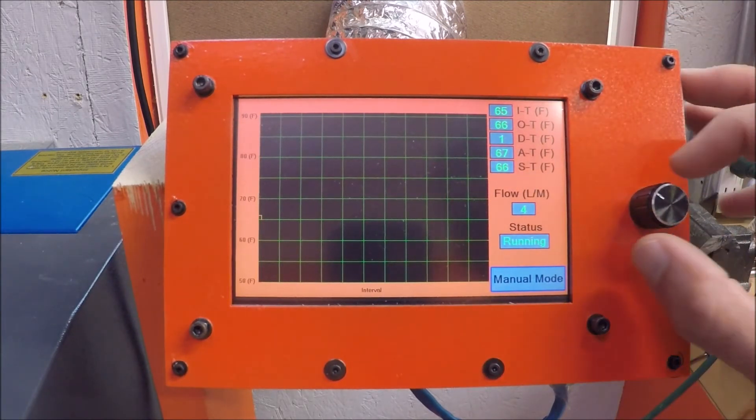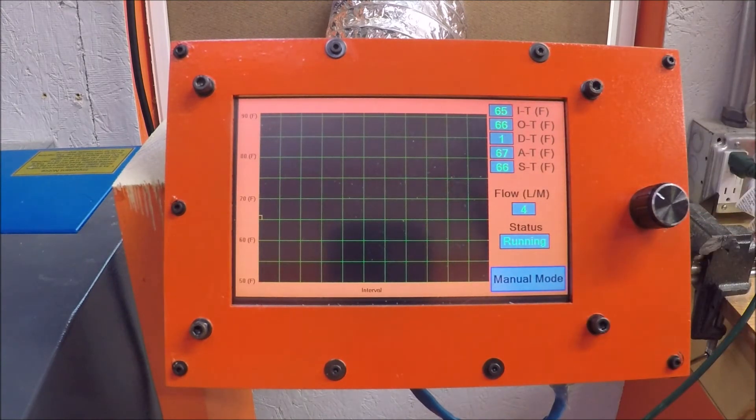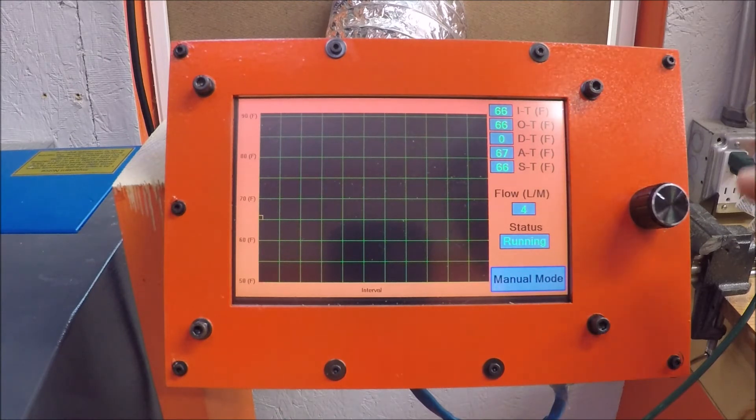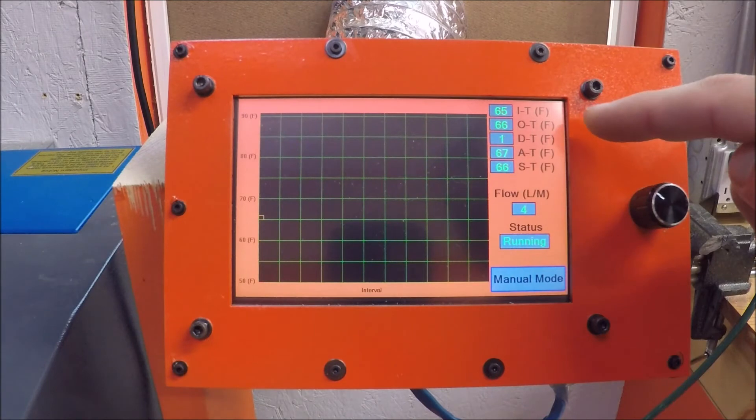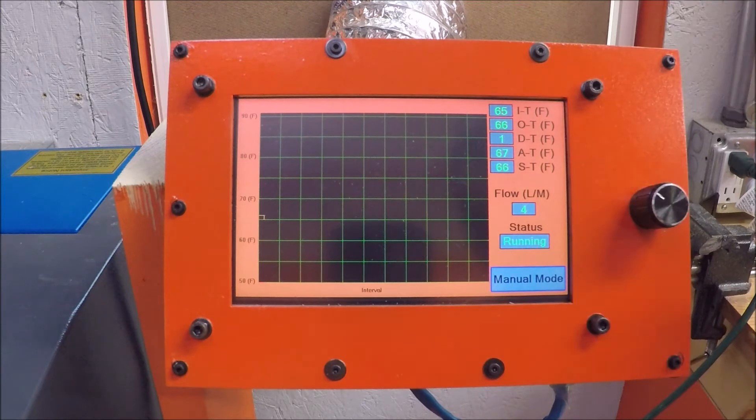You also have this ST. This is a set temperature, and you can move this potentiometer left and right to set that temperature anywhere between 60 degrees, and I think I've got it maxed out at 80 degrees. Now, what this controller will do is it will control the heater and the fans to try to make the output temperature that this chiller outputs match whatever you set it to.